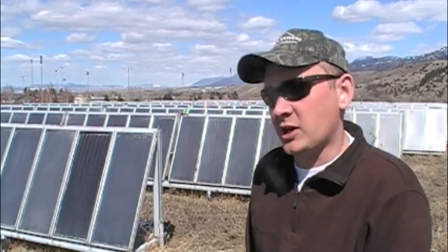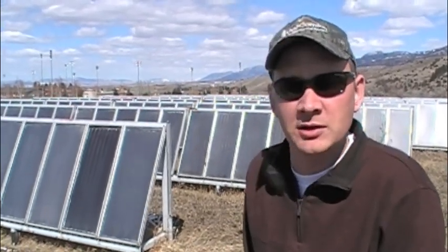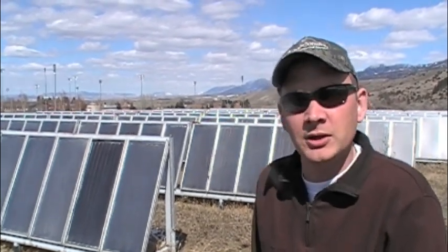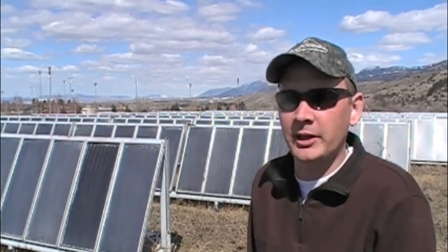And that's simply due to the physics of how we would use the solar collector. In this case, these solar collectors have to deliver the energy at a high temperature — directly to the distribution range. So if the building requires 120 or 140 degree distribution, that's what these things need to achieve in order to begin putting BTUs into the system. But if we can accept energy as low as 40 degrees out of these solar collectors, we can gather a lot more of it and thereby get a lot more value out of the collector.